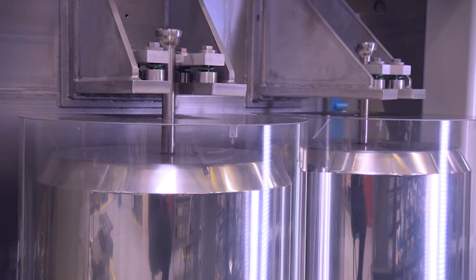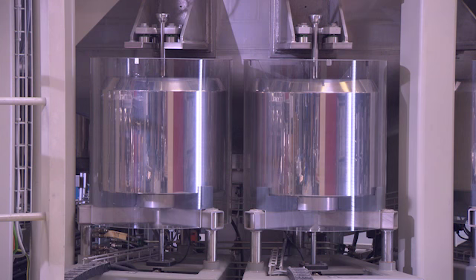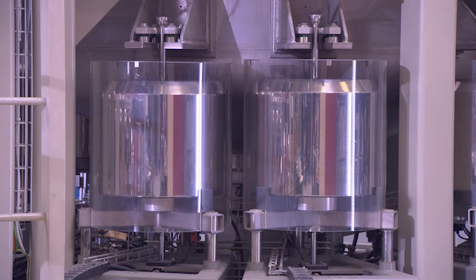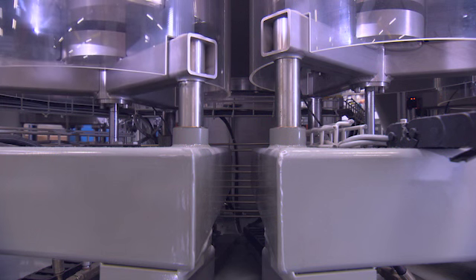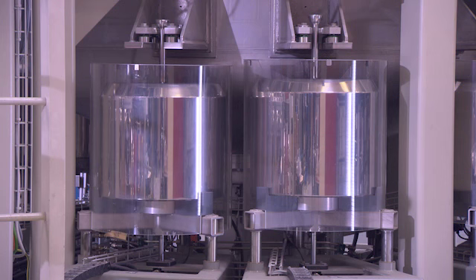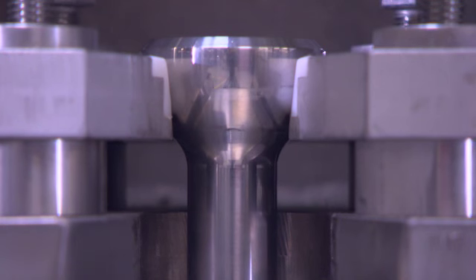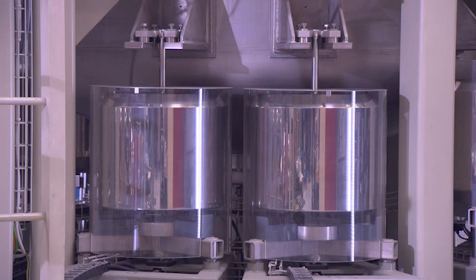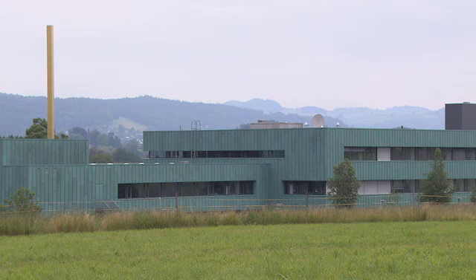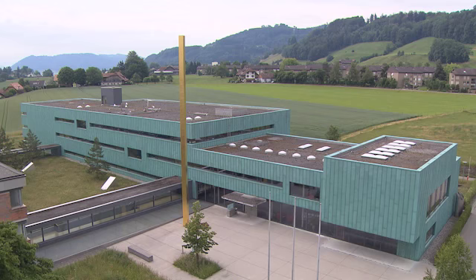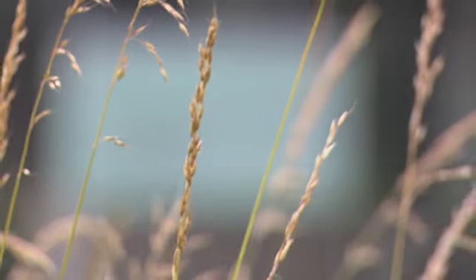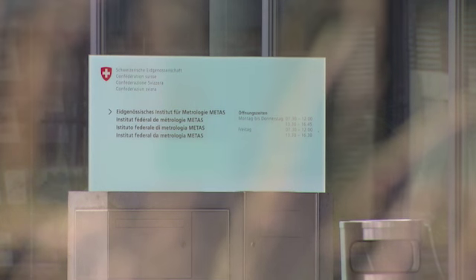Because calibration scales are typically in operation around the clock, they are checked regularly using calibrated reference weights, and if necessary, their outputs are corrected. This is done by hanging the reference weights on the weighing container. The reference weights themselves have to be inspected periodically by a legally recognized metrology institute. In Switzerland, that's the Federal Institute of Metrology, known as METAS.